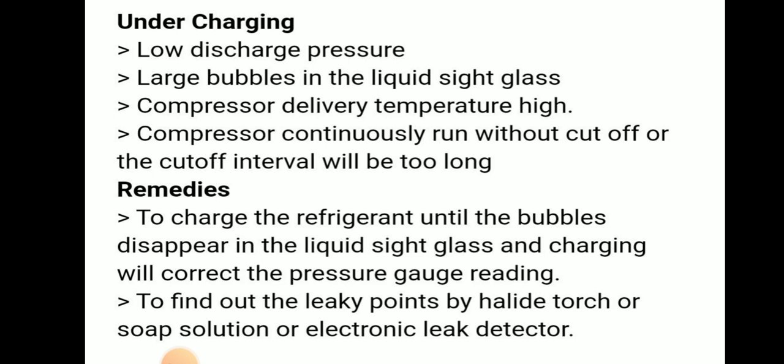Remedies for undercharging: charge the refrigerant until bubbles disappear in the liquid sight glass and charging will correct the pressure gauge reading. To find out leaky points by halide torch or soap solution or electronic leak detector.